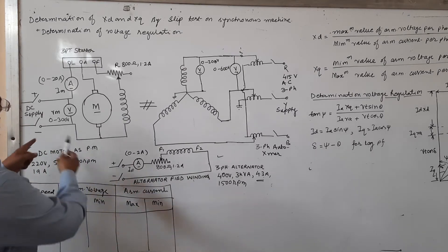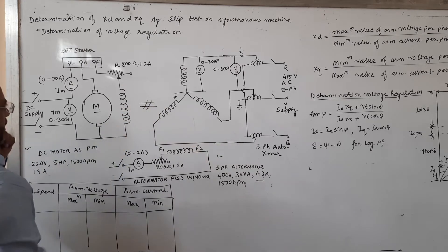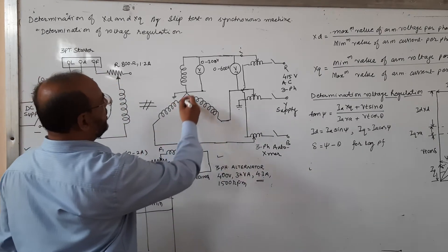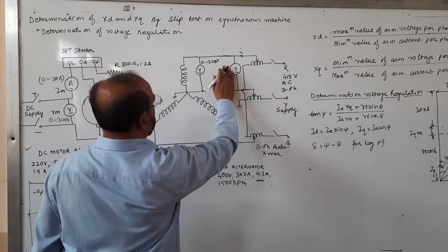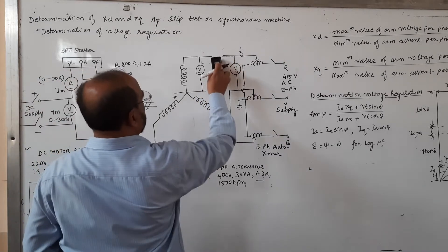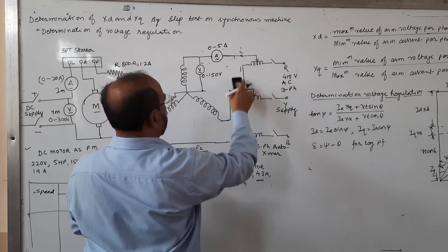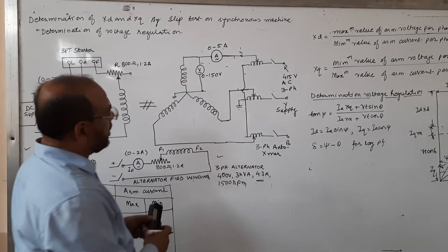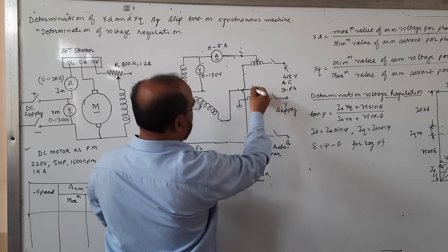This is the practical setup circuit diagram. This is the DC shunt motor acting as a prime mover. The field winding is connected with a rheostat to adjust the speed required by the slip test. This is our synchronous machine, star connected. A voltmeter is connected measuring up to 150 volts per phase, and an ammeter measuring up to 0 to 5 amperes per phase. A three-phase auto transformer is connected between the voltage supply and the machine, with the variable output terminal as the outgoing terminal.